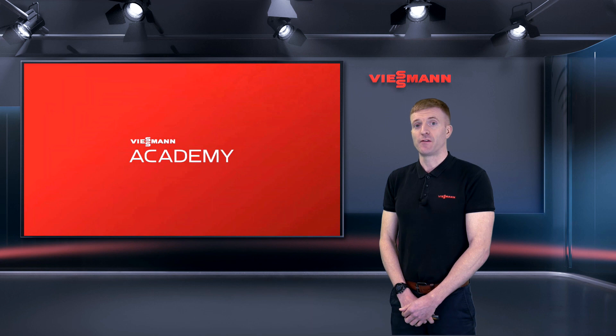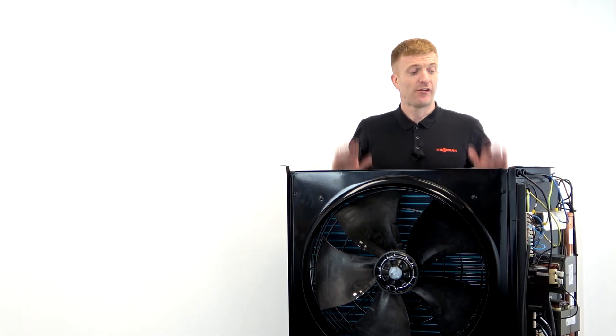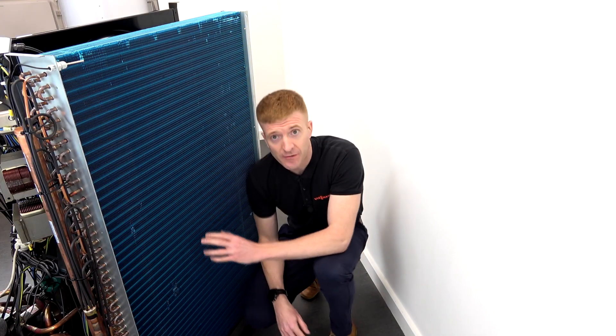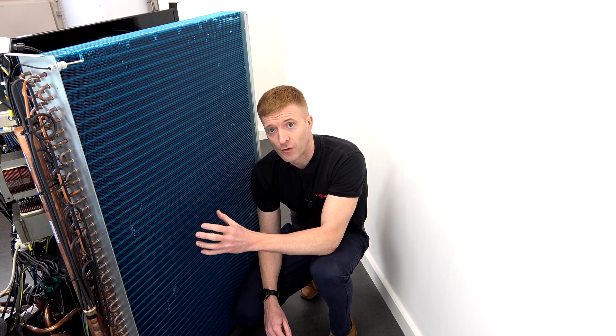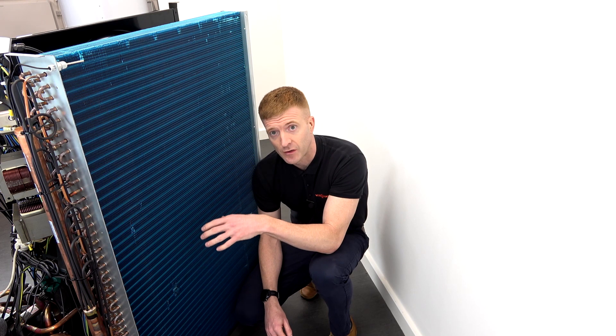The outdoor units for the Vitocal 150 and the 151 are exactly the same. This is the outdoor unit — we've taken all the covers off because we use it for training and demonstration purposes. Starting at the back of the evaporator, this is where all the ambient air is drawn through the aluminium fins, and the heat energy is absorbed into the refrigerant. One thing to note is that the evaporator is coated to prevent corrosion.